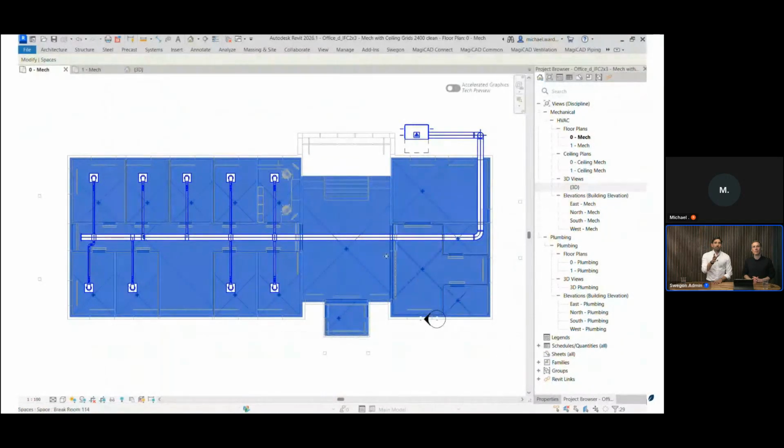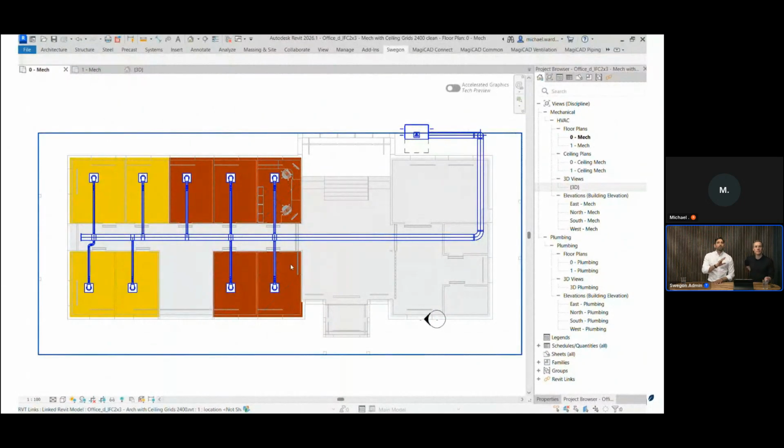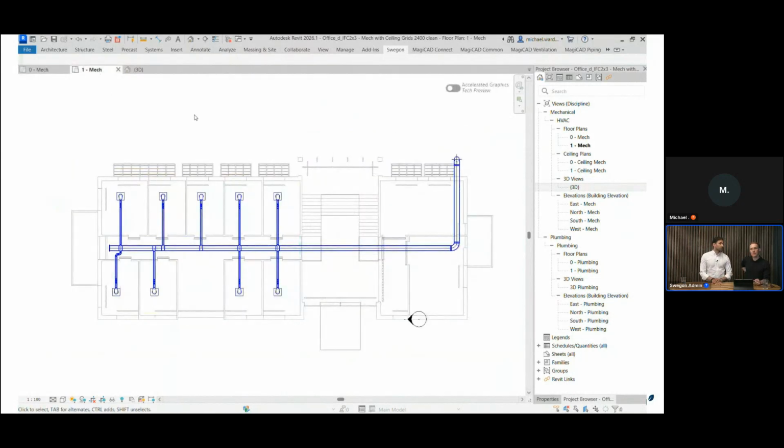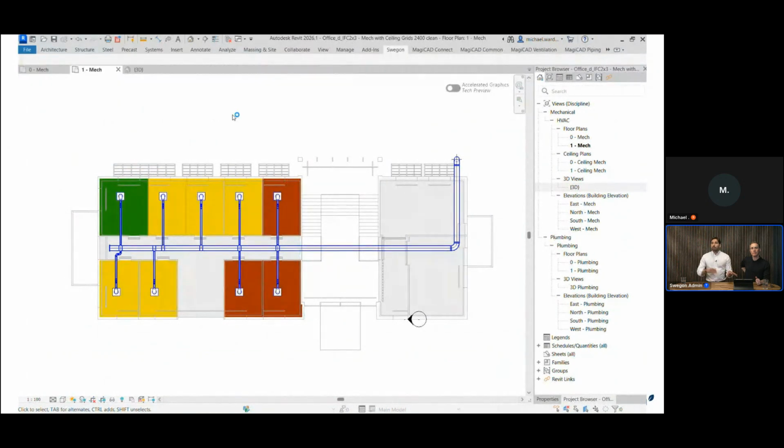Now, it'd be interesting to see where they are. As you can see, the rooms on this particular floor, which is the ground floor, the ones that are closest to the air handling unit, seem to be the ones where we have the largest noise problem. That makes sense. Yeah, that's typical. And then on the first floor, we have a little bit of a better situation, maybe further away from the air handling unit. But still, the rooms closest have the problems.